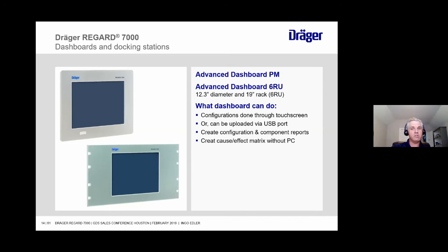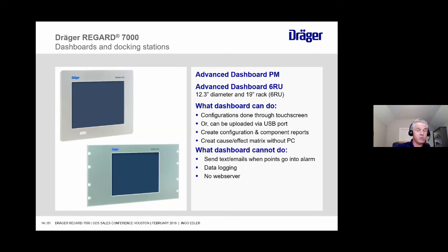You can affect a cause-effect matrix. But what the dashboard cannot do: it can't send texts or emails if any of those points go into alarm. It can't do any data logging. There's no web server, so you can't log into the device from wherever you have internet access and see what's going on with your safety system.